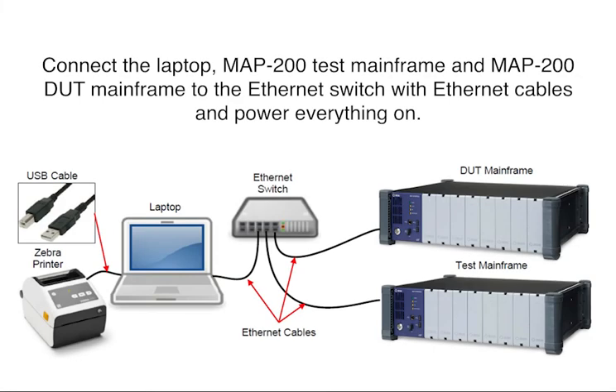To begin, connect all units and power up. This includes connecting the power cables to chassis where the source to be calibrated resides, the calibration kit, the laptop notebook, the Zebra printer and Ethernet switch. Make sure the 4 green lights on both map chassis are lit. Connection instructions are included in the printed comprehensive instruction booklet included in the box and on the VIAVI instruction document located on the laptop hard drive.